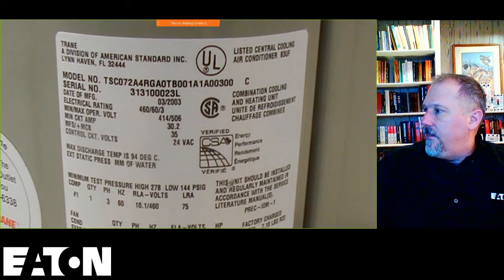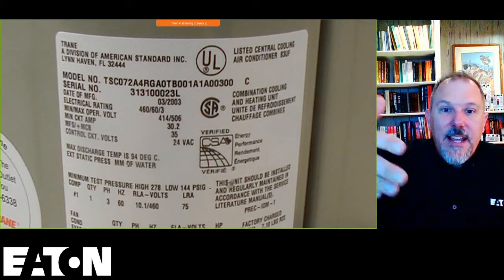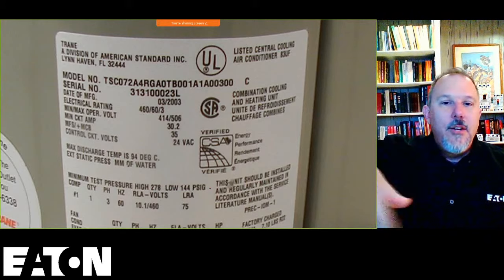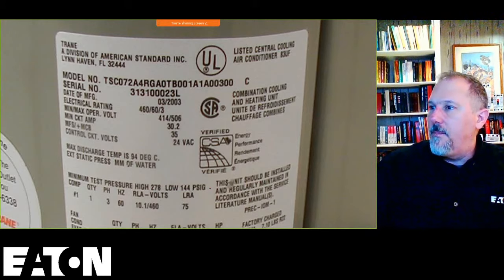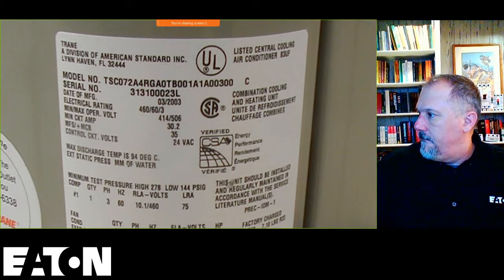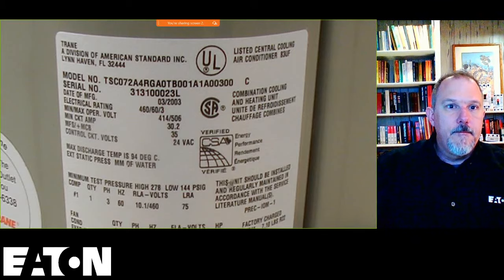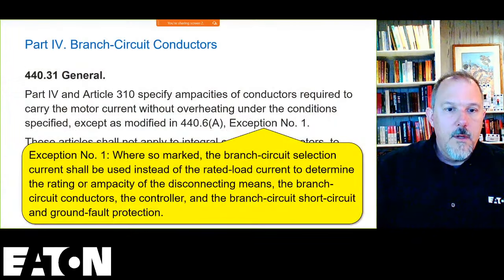What else in this label tells me that it would be a combination load, other than me looking at it knowing, like you said, I know there's a fan in there, I know there's a compressor in there, I know all this other stuff that's inside that unit, but... Well, on the bottom left in your photograph, and you can't see exactly what you need, but it looks to me like it says condenser on the extreme bottom left, right where it cuts off. Factory and then charge, I'm guessing under that it says fan. And that would be your combination. But if your graphic went up another half inch, I think we'd be there.